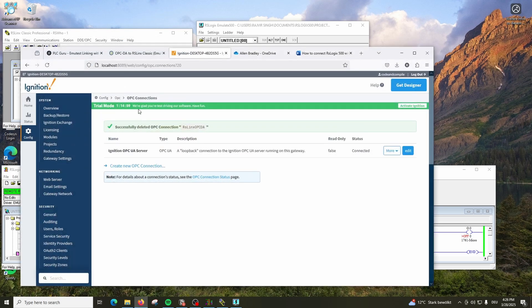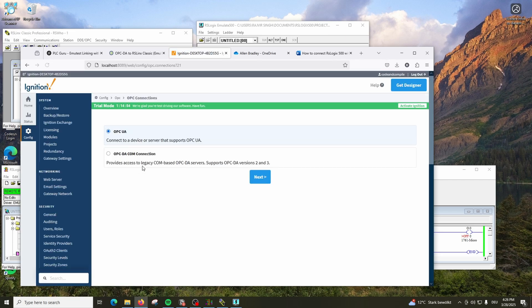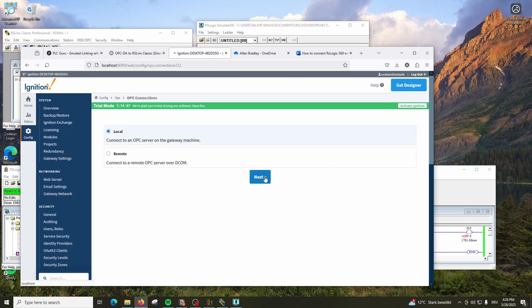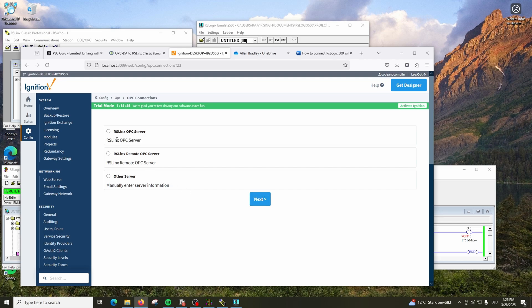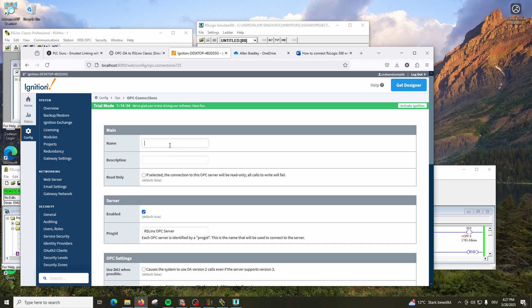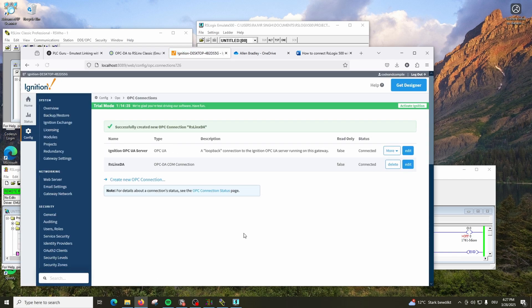Now go back to Ignition. In Ignition, create a new OPC connection. Instead of OPC UA, select OPC DA. Click Next, go to Local, click Next. You will see automatically RSLinx OPC server is here. Select the local one since your server is running locally. Click Next and give it a name - I'll call it RSLinx DA. Create the connection. You will see the status as Connected.